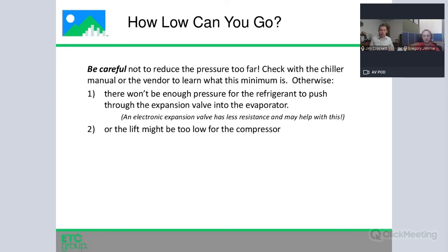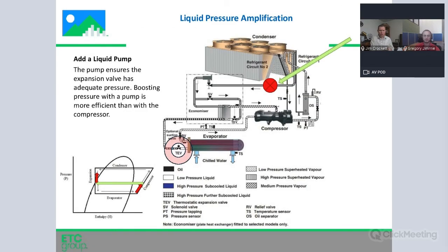Now, addressing the expansion valve, you can go with an electronic expansion valve. That has less resistance, which may buy you some room. But one other thing you can do is add a liquid pump. Once the liquid has condensed, and it's borderline, if it's just barely outside of the dome and you're worried that it's going to warm up and start to flash on its way to the evaporator, you can add a liquid pump. Just from an efficiency standpoint, it's much more efficient to use a pump to pump a liquid than it is to use a compressor to squeeze a gas. You're looking at like 70 or 80% efficient rather than 30% efficient.